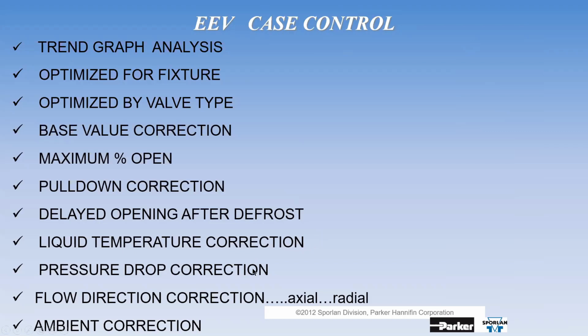Pressure drop correction. Okay, is this case 500 feet away from the rack? Yeah, there's going to be a difference in pressure drop going across that valve. Flow correction, based on whether the flow is coming in axially or radially, and then ambient correction. Not everybody uses this, and I wish they would. If it's February and the store is 72 degrees, but it's at 42 relative humidity, that's different than if it's August and the store is in Louisiana and it's 76 degrees and it's 60% relative humidity.